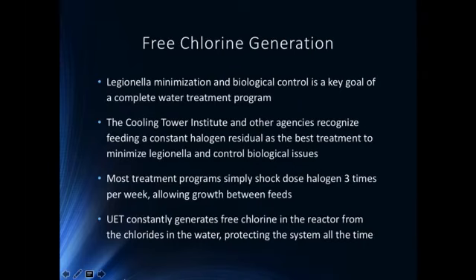The reason most people don't is it just simply is cost ineffective to feed that much product and keep it in there all the time. And so what happens is traditional chemical programs feed biocide a couple times a week, 2, 3, 4 times a week maybe, feed a high amount, and then let the bacteria start to grow again for a period of time and then shock it again. Again, it's technology that's been going on for many years, but by keeping a constant residual, we keep that secondary growth from happening, and we keep that biofilm down all the time. And again, from a Legionella minimization standpoint, a really big game changer.